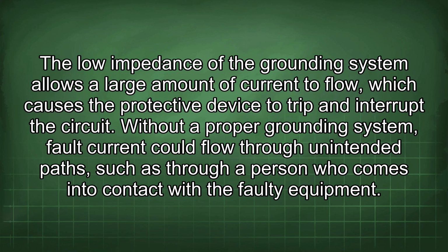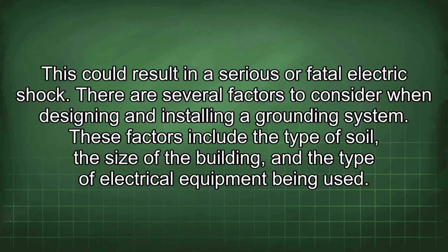Without a proper grounding system, fault current could flow through unintended paths, such as through a person who comes into contact with the faulty equipment. This could result in a serious or fatal electric shock. There are several factors to consider when designing and installing a grounding system. These factors include the type of soil, the size of the building, and the type of electrical equipment being used.